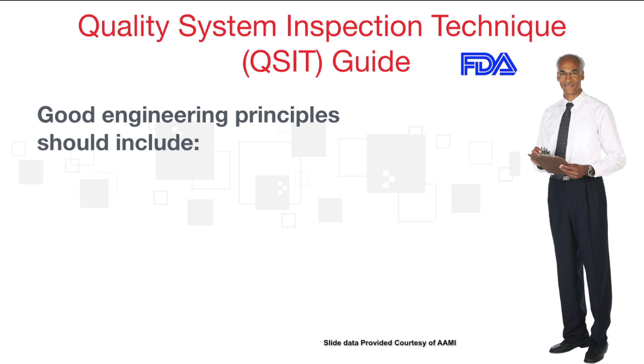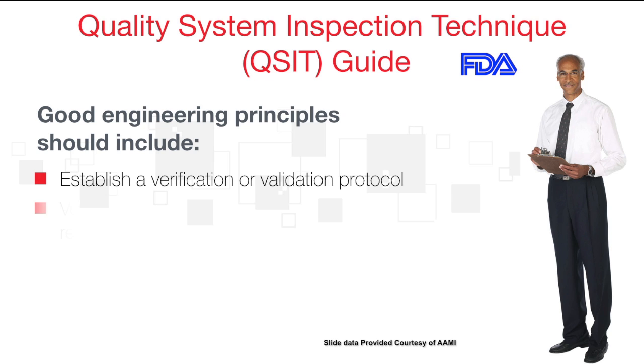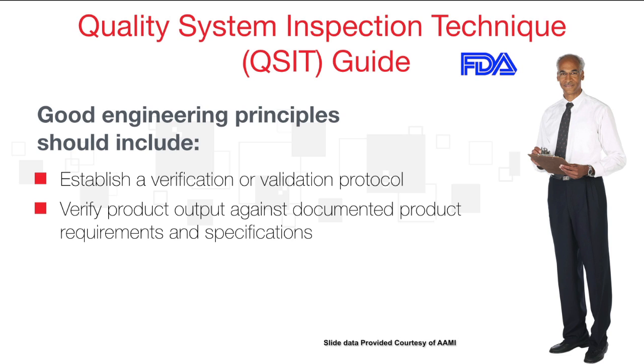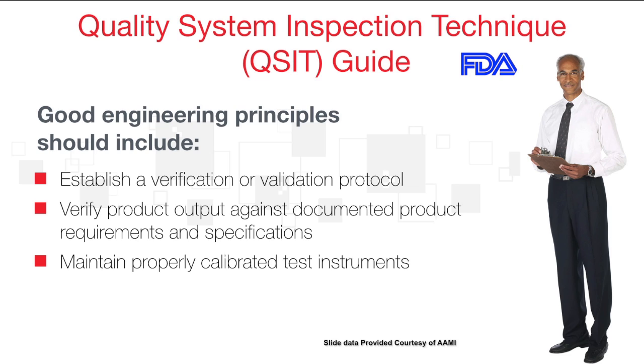Now, for those of you that don't remember, QSIT simply is the FDA Bible. It stands for the Quality System Inspection Technique. And there are some good principles here. They overlay some good engineering principles, such as engineers would establish a verification or validation protocol, verification output against the documented product requirements and specifications, making sure that the test instruments that I'm going to use are up to date, maintained, and calibrated. So a couple things to check as far as a good engineering concept also applies to our verification and validation.